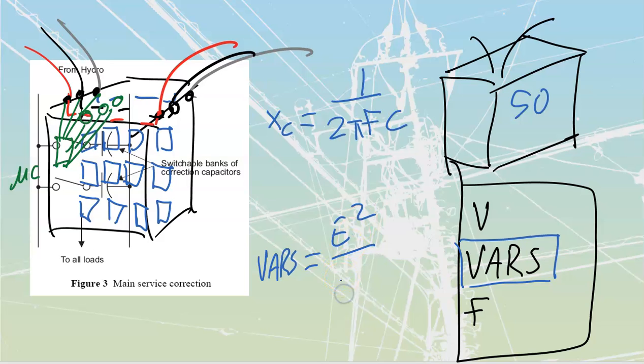My form of R is going to be my XC here. So we're going to find out what happens to my VARs when my XC changes. XC is going to change because we've increased frequency — it's rated for 50 hertz, but we're now scabbing that onto a 60 hertz system. If F, my frequency, goes up, the capacitive reactance of that equipment is going to go down.